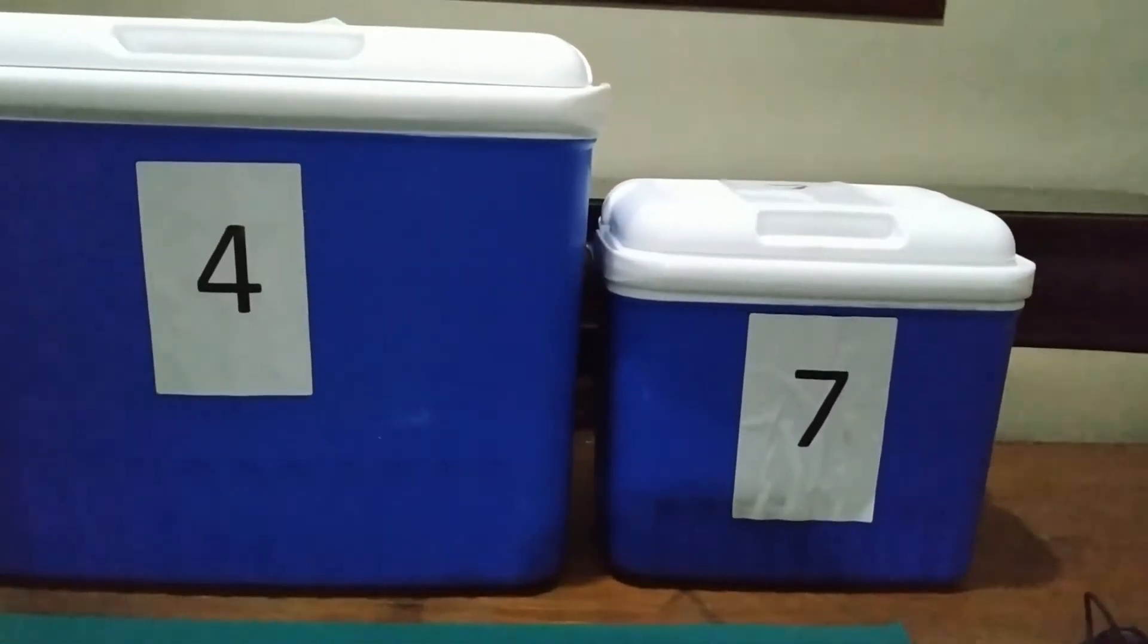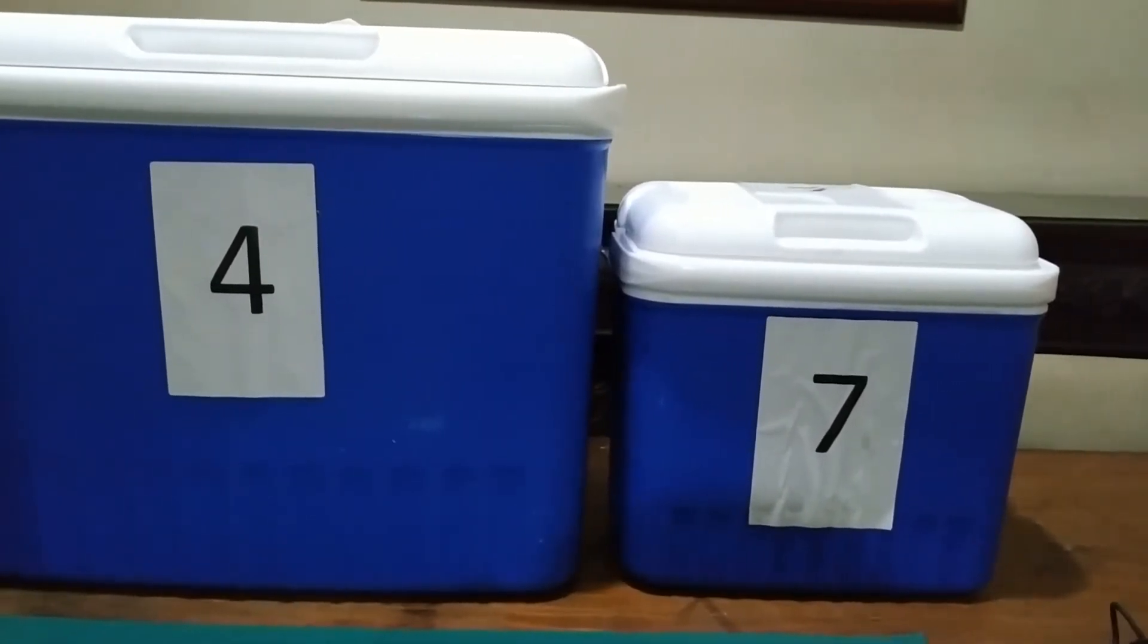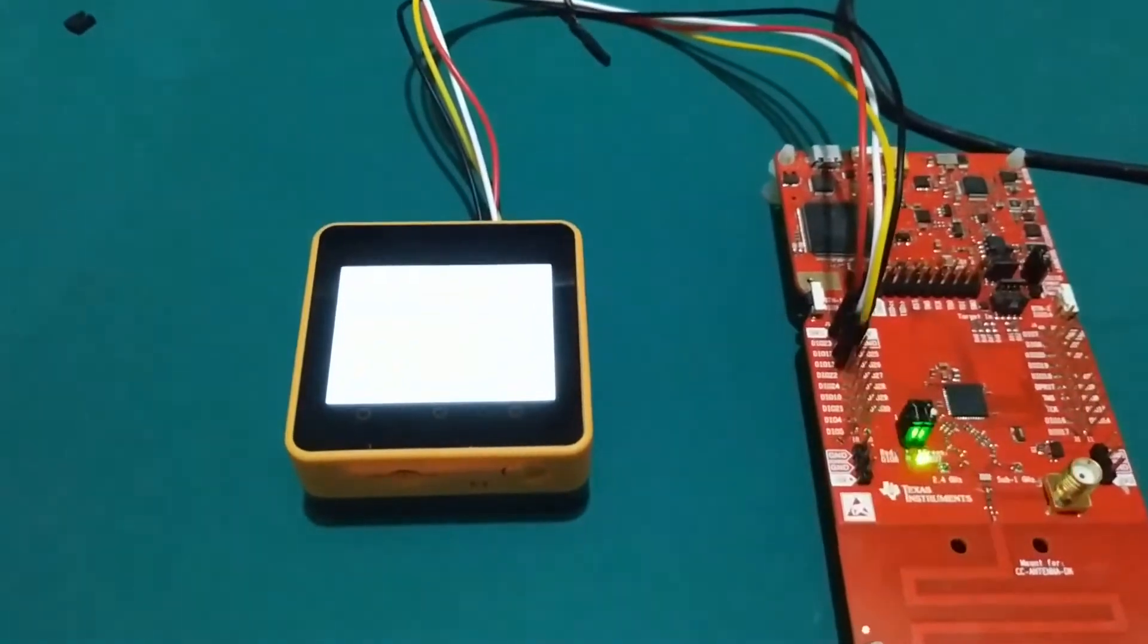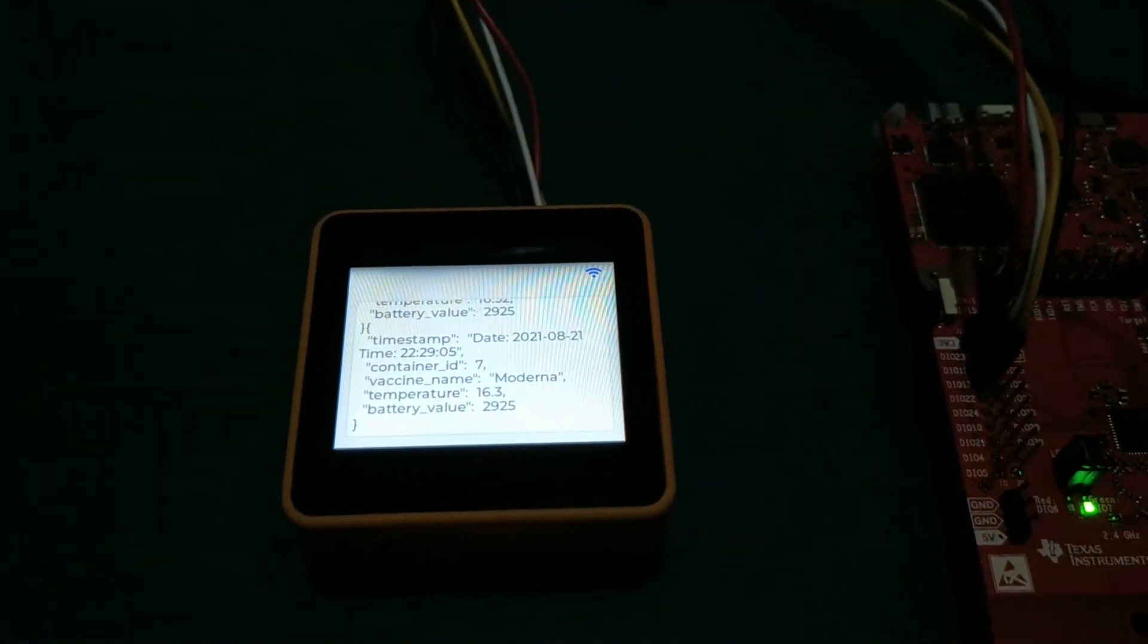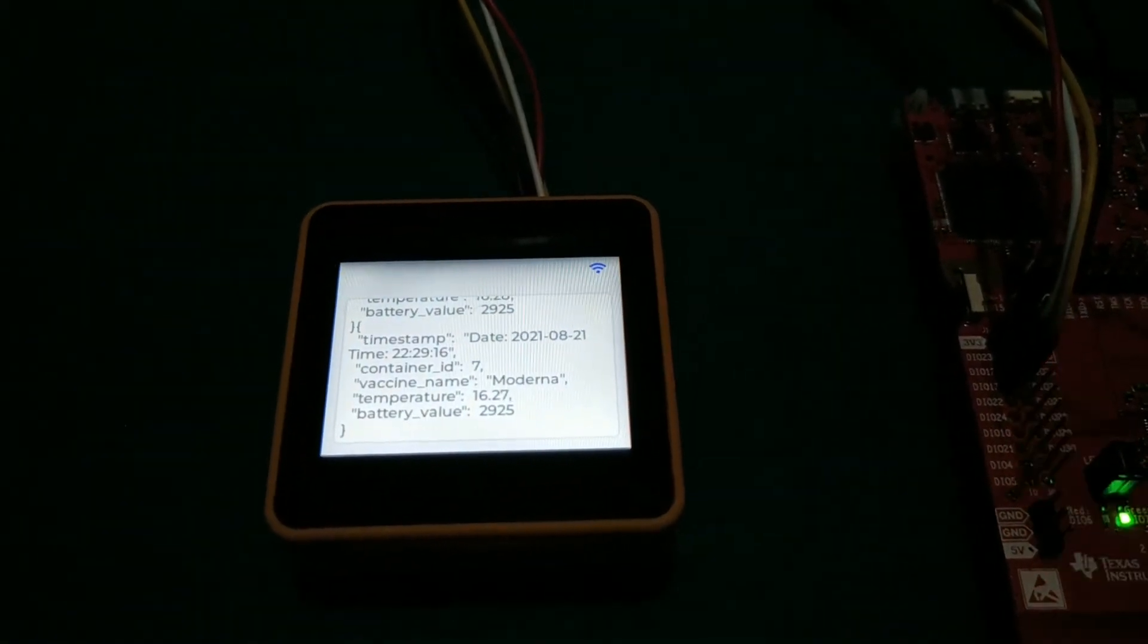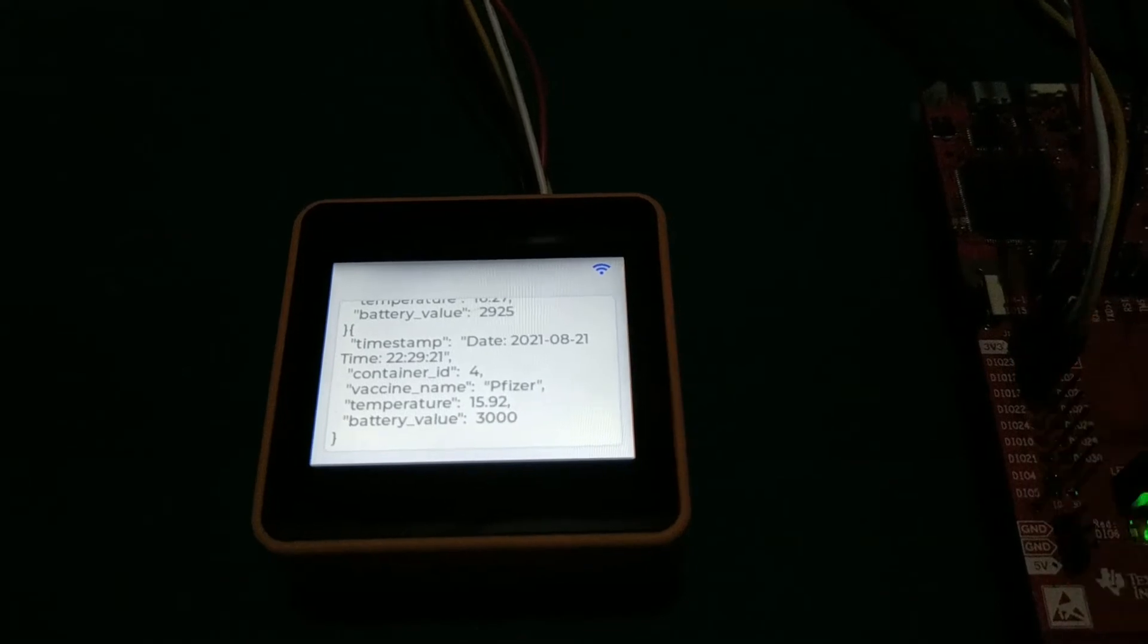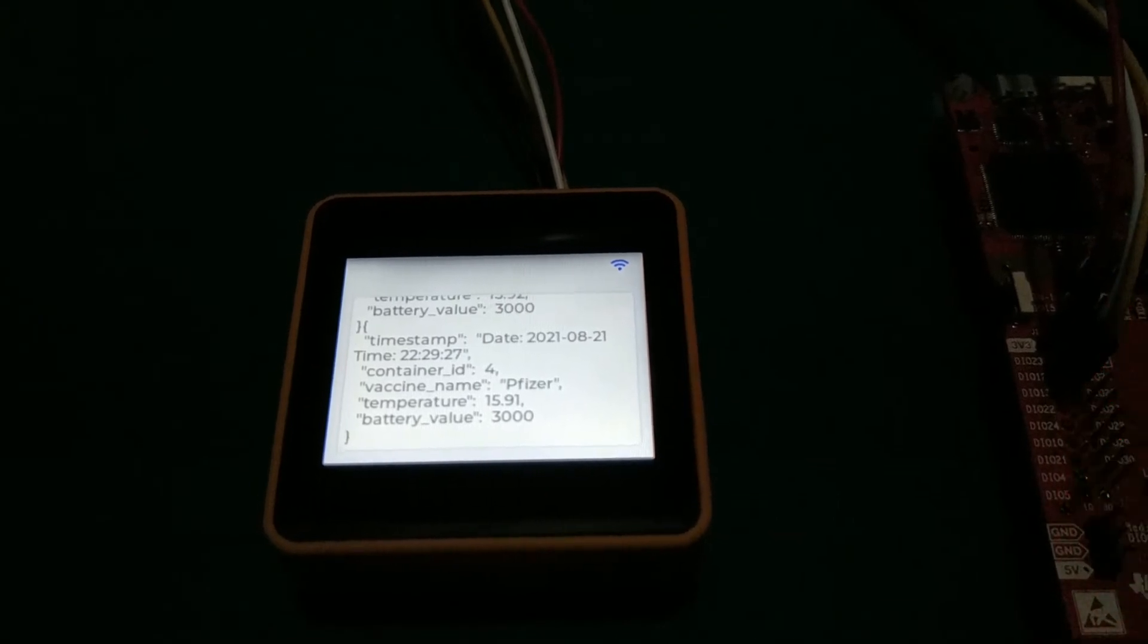The readings from both sensor nodes are within the set temperature range of 2 degrees minimum and 25 degrees maximum. The reading from container ID 7 is 16.27 degrees Celsius. The reading from container ID 4 is 15.92 degrees Celsius.